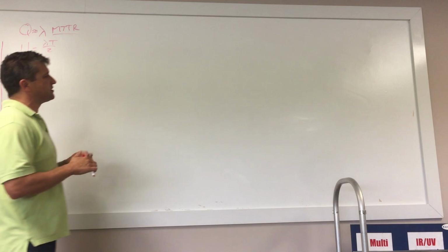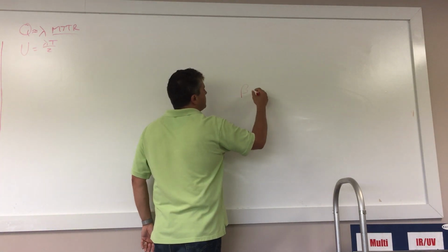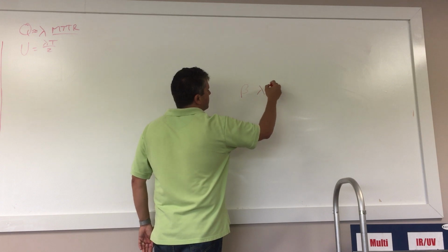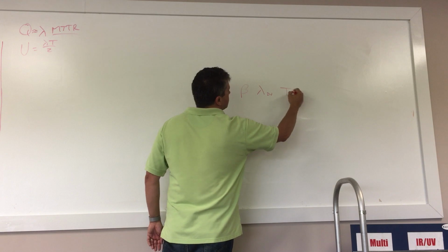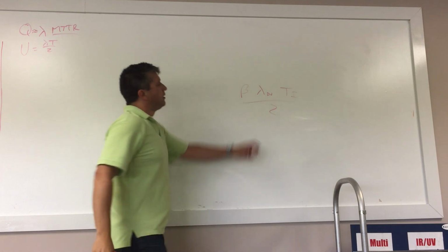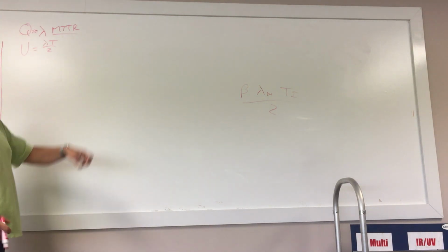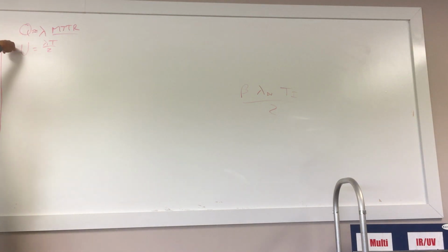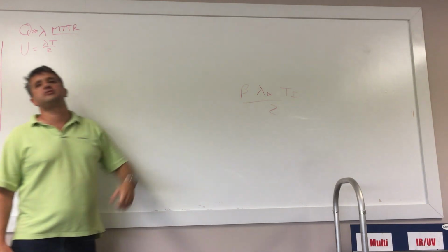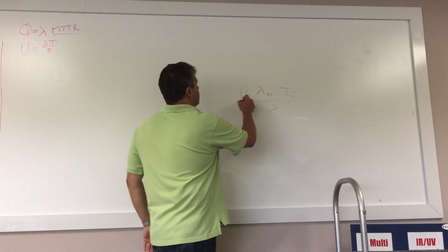in just a second. So what the beta term is, is beta times lambda DU times test interval over 2. Lambda t over 2 tells me this is an unreliability, and the difference between the beta factor term and the normal DU term is this beta multiplier.